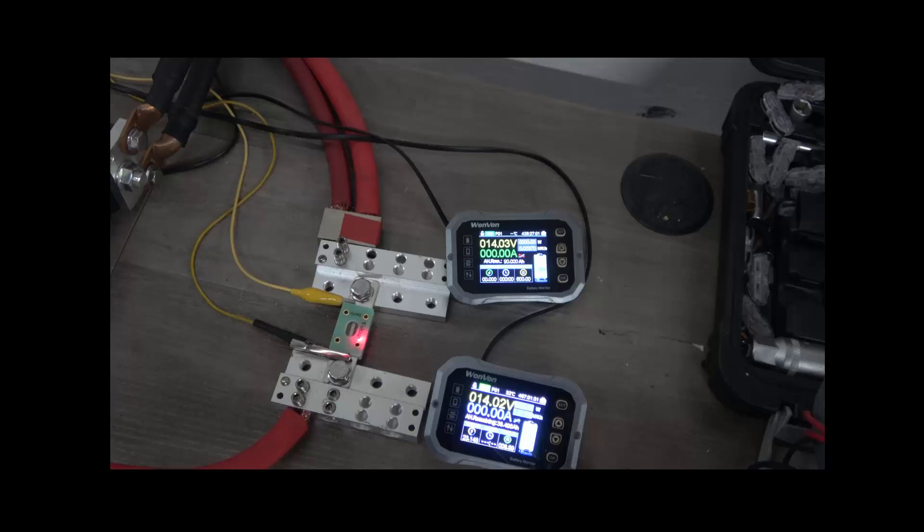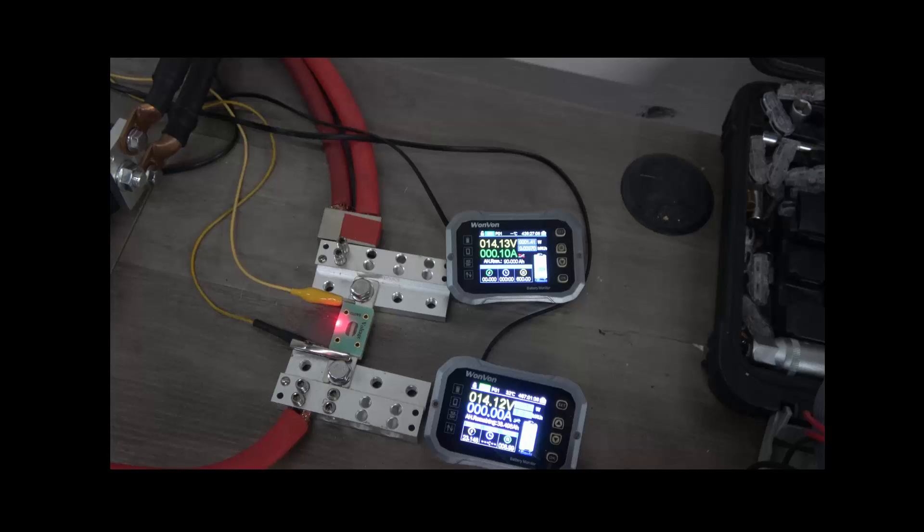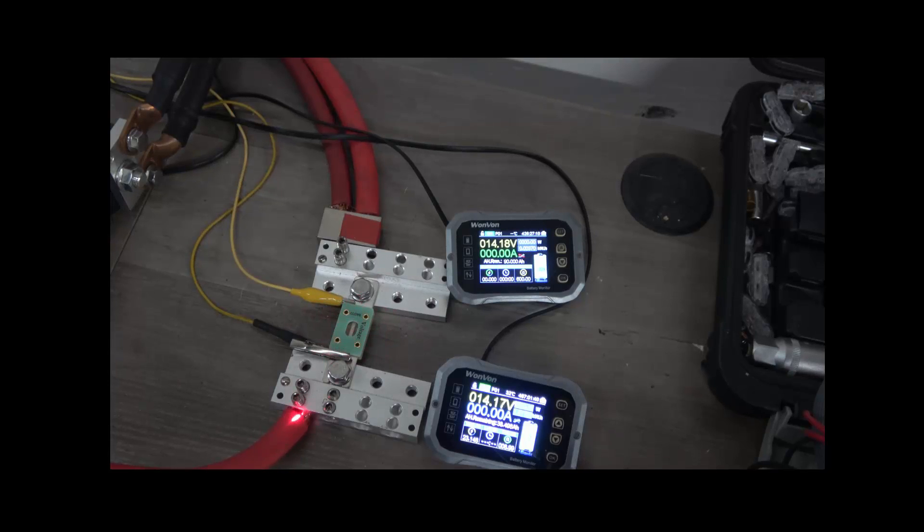And the final temperature is about 107, 108 degrees on this fuse, so well within normal operating temperature.